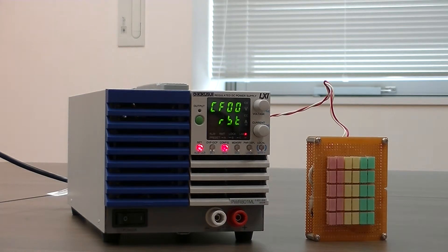Next, we have our soft start and soft stop settings. This allows us to control the speed of our power supply's rise time from 0.05 to 10 seconds, which limits inrush current and is much gentler on the product that we are testing.